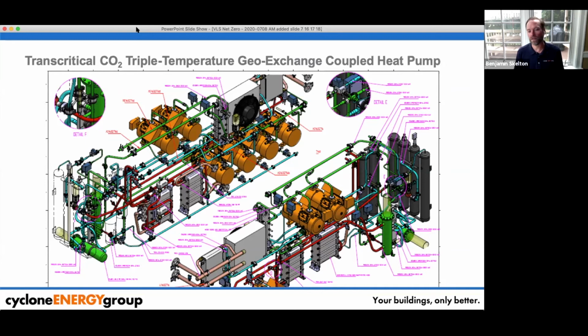And so the triple temperature means that we make chilled water, we make heating hot water, and we can relieve the energy off the refrigeration cabinets, all at the same time. What I find still to this day extraordinarily fascinating about this machine is we make 165-degree hot water, which most heat pumps don't do anything more than 130 degrees, because they have a refrigerant that's gonna blast off at 130 degrees, so you're kind of limited there.